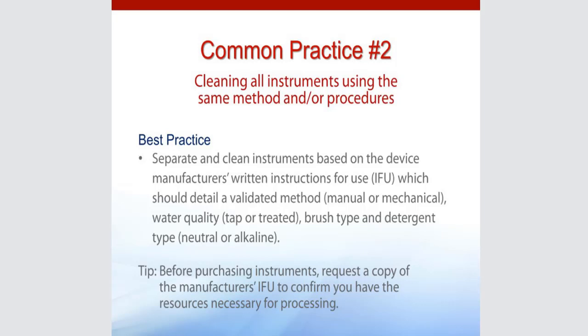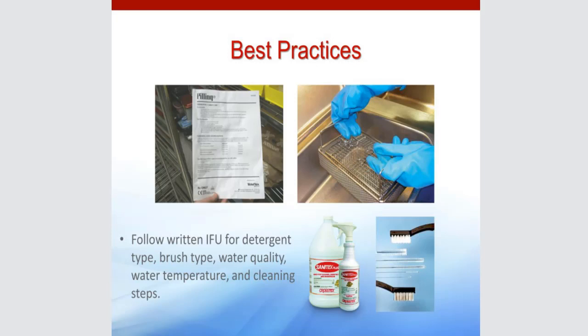You also need to look, if you are using any type of brush on your instruments, you want to make sure that it's compatible, as well as the detergent type that you're going to be using in your ultrasonic or your instrument washer. Using an over-the-counter product, you cannot use a dishwasher soap in your washer disinfector. It's a medical device, and it requires a specific type of neutral or alkaline detergent to be used in there. And when you're thinking about replacing instruments, maybe before you even buy the instrument, request a copy of the IFU for that instrument to make sure that you have all the resources and knowledge necessary to be able to process that particular instrument as well.